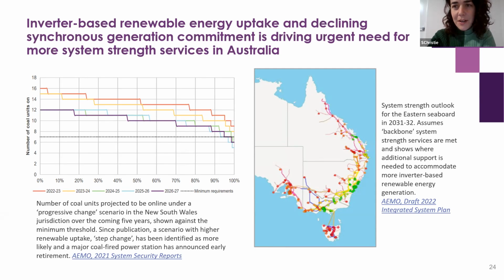With system strength, the way we generally summarize it inside AEMO is that it's our way of describing how to keep the voltage waveform stable and in good shape, both before and after a fault or disturbance on the system.